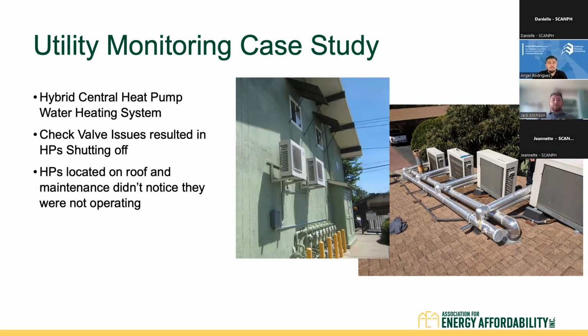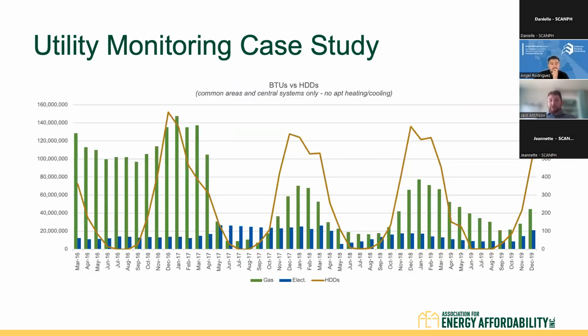And then the heat pumps were located on the roof, and maintenance did not know that they were not operating, because you can typically hear a heat pump, but if it's on a roof, you won't be able to hear it. You won't be able to see that it's operating. The reason they weren't operating is that check valve issues resulted in the heat pump shutting off. That could have been caused by hard water. Again, this is why it's important to flush those systems frequently. Next slide, please.